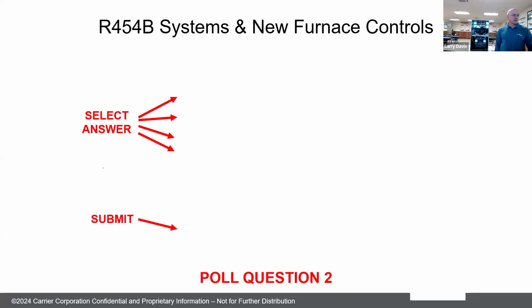All right. Almost 94% of our group answered the question, so let's go ahead and share the results. At 110 volts, what amperage is considered an ignition source? If we remember from our chart, it was that highest number, 57 amps, well above any ancillary device or auxiliary device or accessory that we'll have in our system. So most everybody got that answer. We'll stop sharing. Another question has come up here. Will the ports on the unit be left-hand thread?